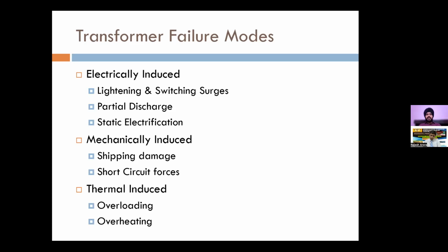And then there is a thermal failure mode, thermally induced failure, which can be due to overloading or overheating. Overloading can be due to the transformer facing loads more than its capacity for a short time or a continuous period, like what we are seeing recently for the renewable generating stations, where the renewable energy is getting pooled. So overloading, particularly when the solar is at its peak, is often observed. So nearly for 8 hours, it is loaded to near its full capacity, and then afterwards it comes down almost to nil load. So this type of temporary overloading, or overloading for a short period, can also cause failures.